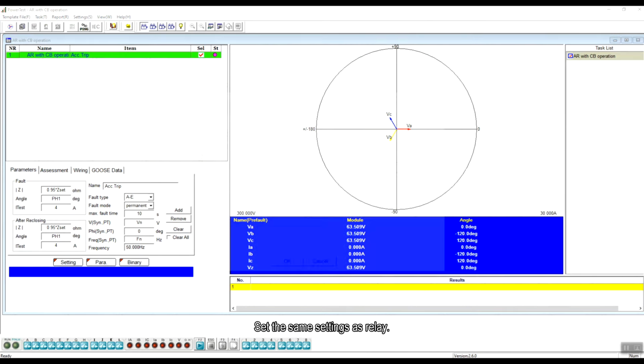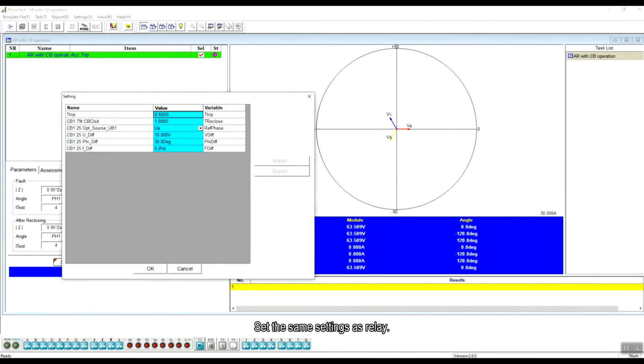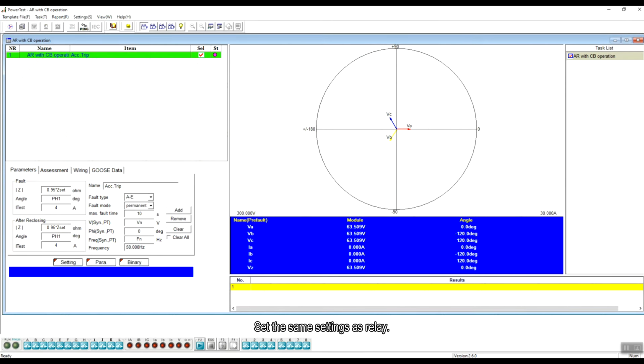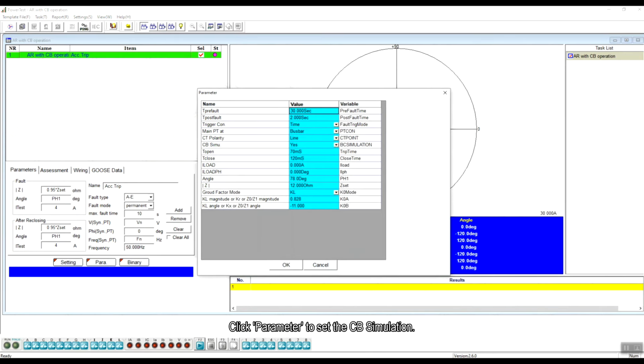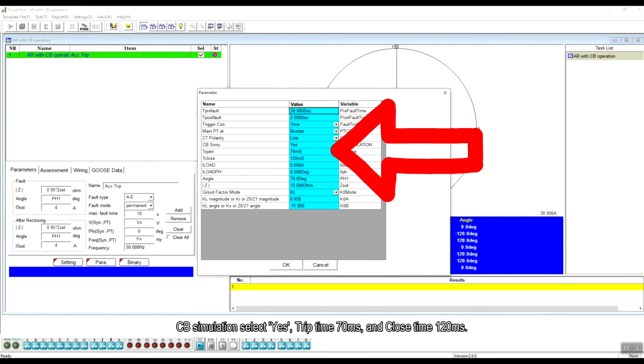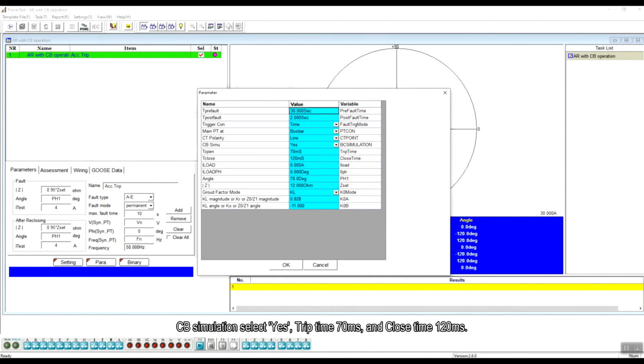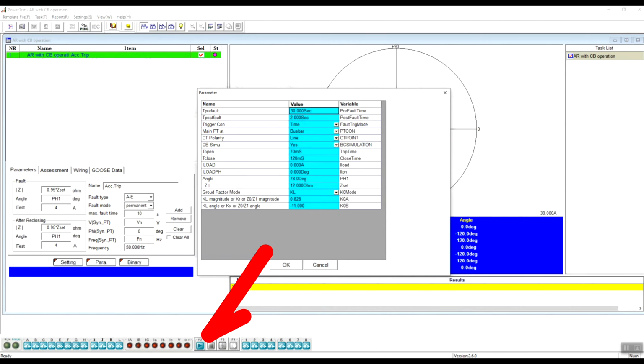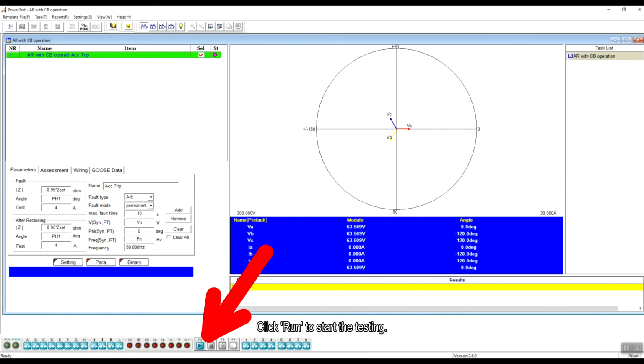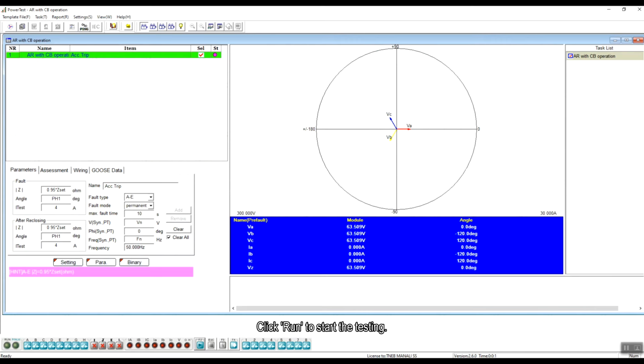Set the same settings as relay. Click Parameter to set the CB simulation. CB simulation, select Yes, trip time 70 milliseconds and the closing time 120 milliseconds. Click Run to start the testing.